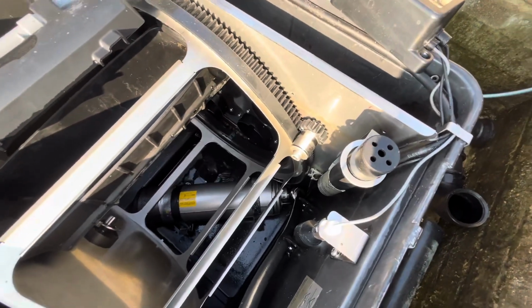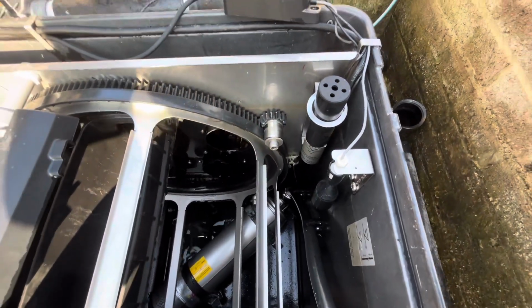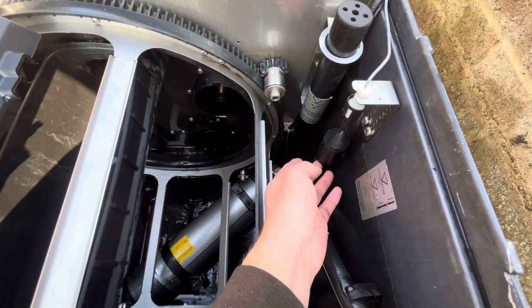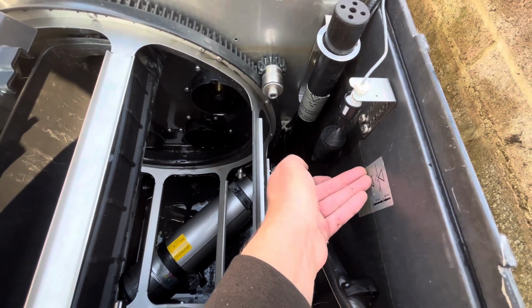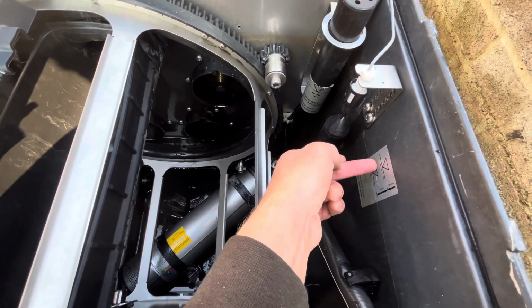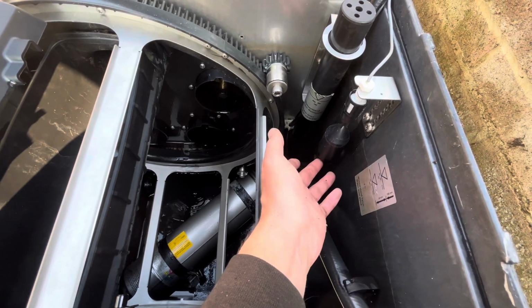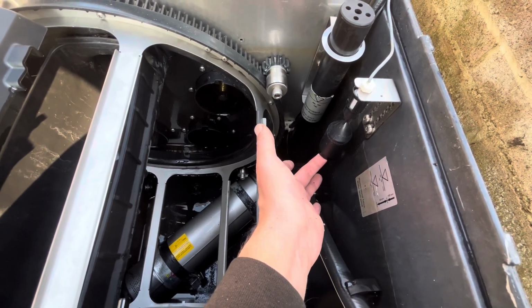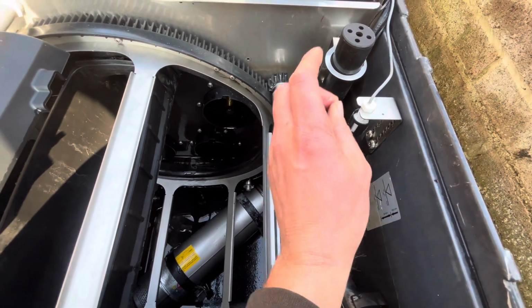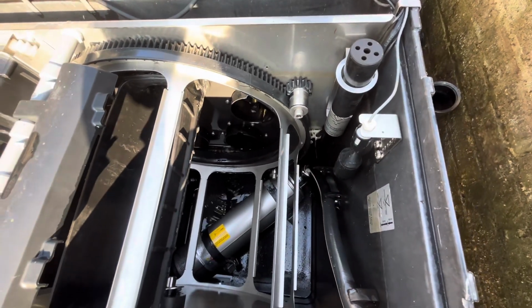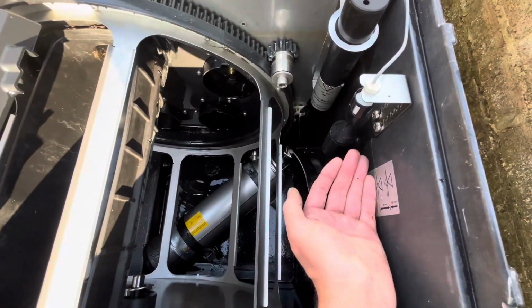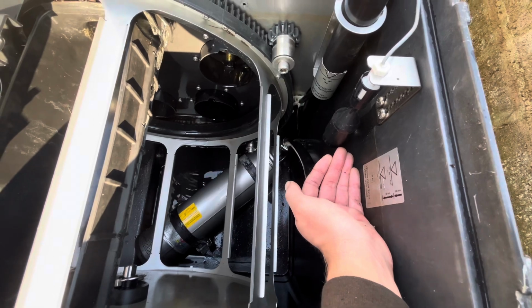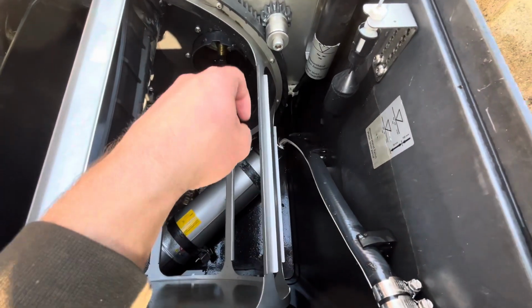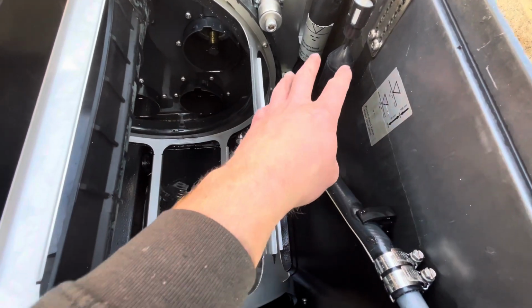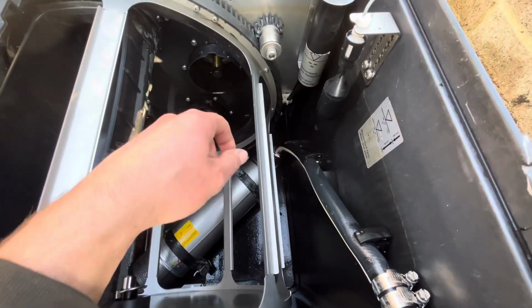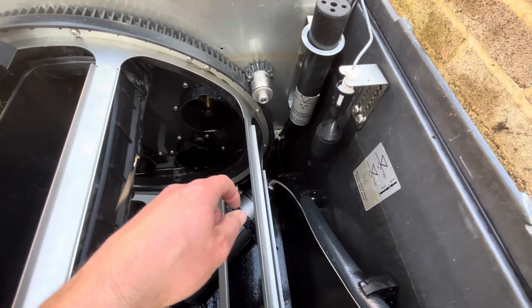It doesn't actually control the pump, but it will tell if the pump turns off for any reason, the water level will then rise up in the drum, and it gives you the install line here. If the water rises up to that, it will push this sensor up, and that will say to the control panel that it doesn't think the pump's running, because you get residual drop on here from it running, and the water level will actually run lower. That should always be down, so it thinks the pump is continually running.